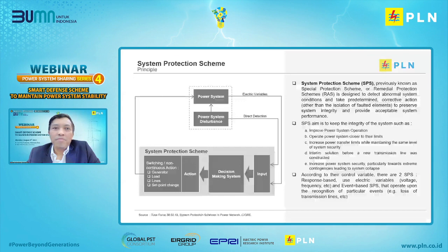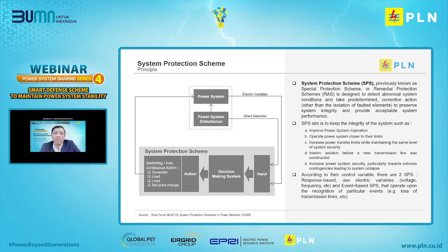According to the CIGRE Task Force report, the System Protection Scheme or Remedial Action Scheme, originally called the Special Protection Scheme, is designed to detect abnormal system conditions. It takes predetermined corrective action to maintain system integrity. From the block diagram on the screen, we can see that SPS gets input in electric variables, which we can call response-based SPS, or direct detection, which we call event-based SPS. These inputs will be processed to decide what action will be taken.